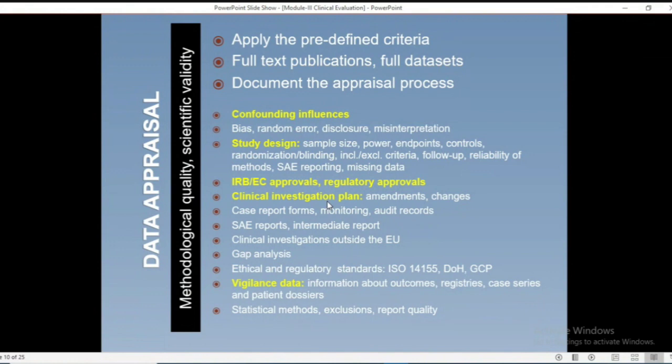Clinical investigation plans. All this should be in the clinical file. A case report form, monitoring audit record. If one patient is affected by my device, then it is mandatory to fill a case report form. Those report forms should be in the clinical file.